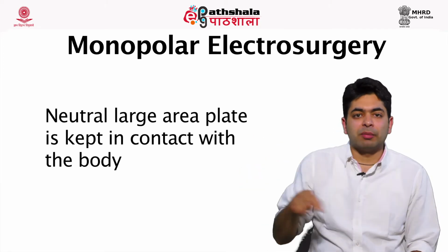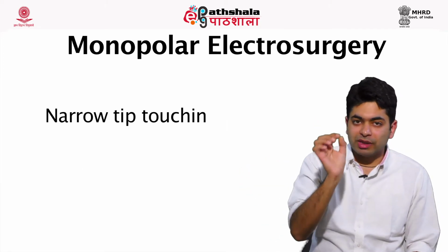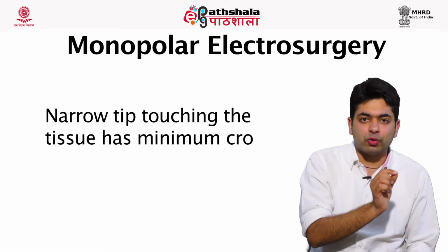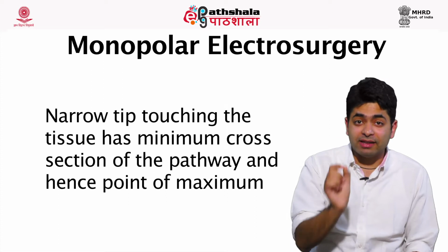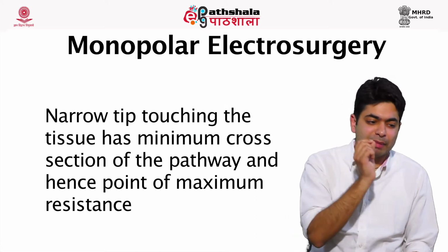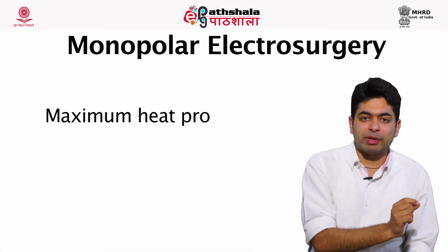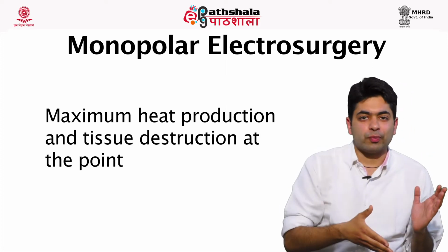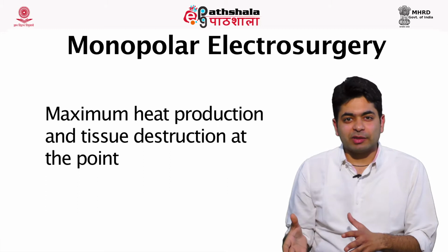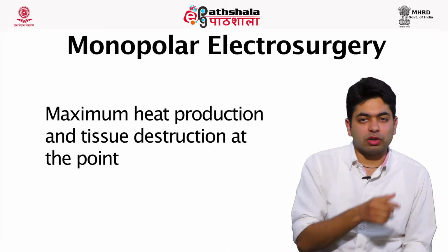So, this circuit is completed, and when the narrow tip of the probe touches the tissue, that point is the narrowest point of the circuit, and hence that is the point at which there is maximum resistance and maximum temperature elevation, and hence the tip of the probe cuts the tissue. It can be used in various aspects. It can be used for cutting and also coagulating.